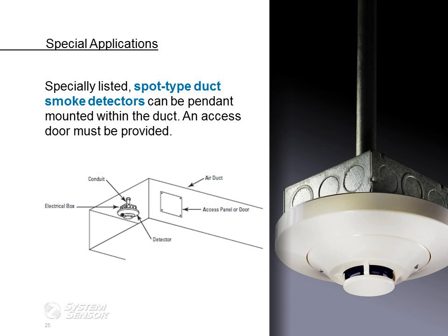Because if you remember earlier, we talked about duct detectors work off the pressure differential of the airspeed. If there's not a minimum of at least 100 feet per minute, then we can't get appropriate pressure differential between the sampling tube and the exhaust tube. So a standard duct detector would not work in that application because it requires airflow to draw the sample in.